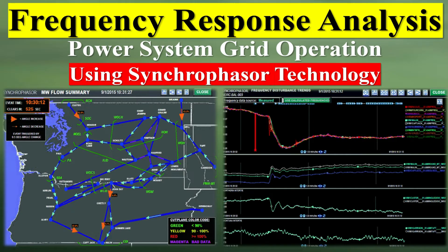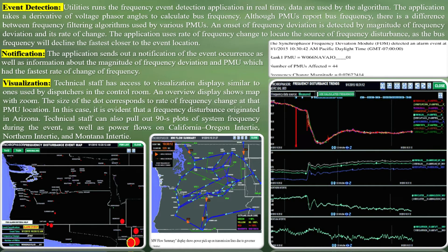Frequency response analysis — power system grid operation using synchrophasor technology, event detection. Utilities run the frequency event detection application in real-time; data are used by the algorithm. The application takes a derivative of voltage phasor angles to calculate bus frequency. Although PMUs report bus frequency, there is a difference between frequency filtering algorithms used by various PMUs. An onset of frequency deviation is detected by the magnitude of frequency deviation and its rate of change. The application uses rate of frequency change to locate the source of frequency disturbance, as bus frequency will decline fastest closer to the event location.